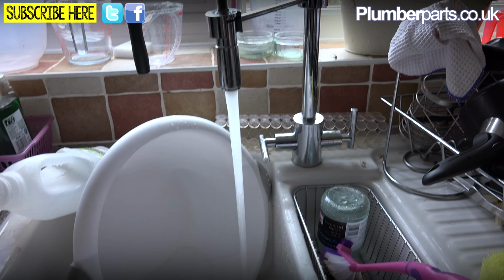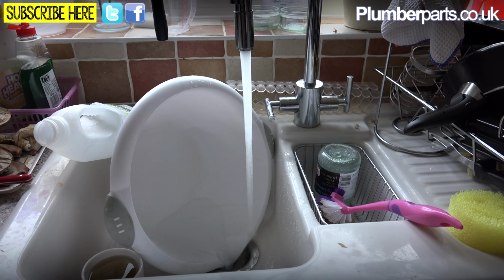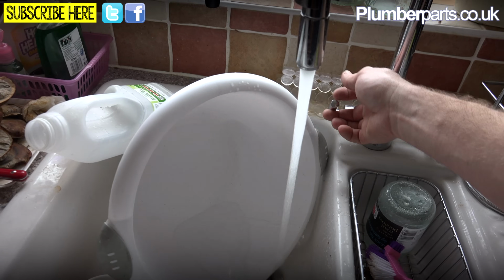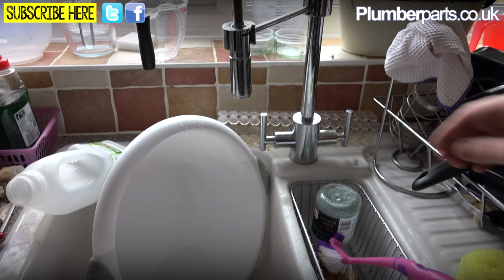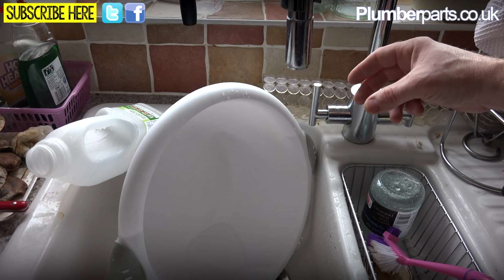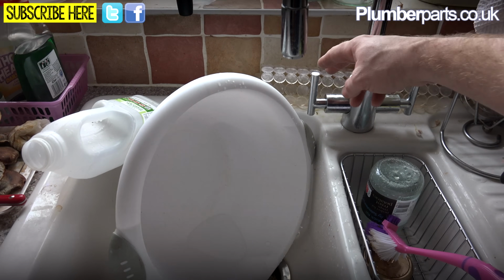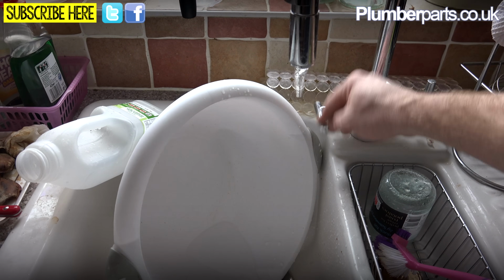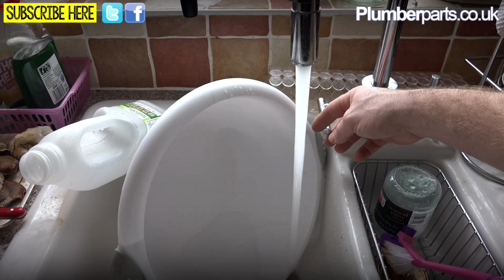Oh my God. That is brilliant. That's worked so well. As you can see, when you turn it on, it just lags for a sec because it's waiting for its little flow switch to prove. So you look, lags, and then bang, comes on. Lags, bang, comes on. How about that?